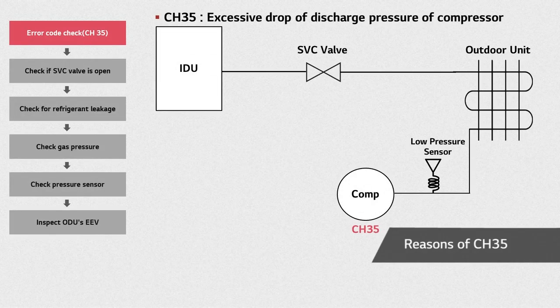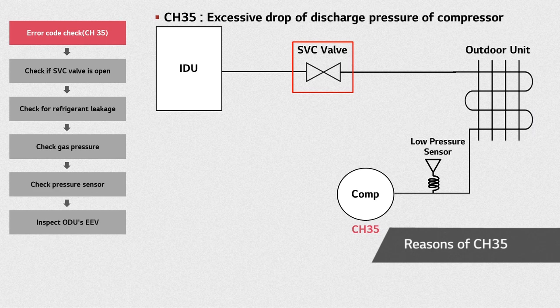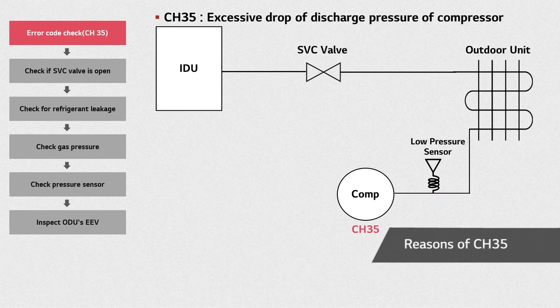CH35 is an error related to a drop of the compressor's discharge low pressure. Low pressure drop will cause the compressor to remain in off state. Common causes of this error include service valve blockage, lack of refrigerant, defects in the low pressure sensor, a malfunction of the IDU's or ODU's EEVs, etc.